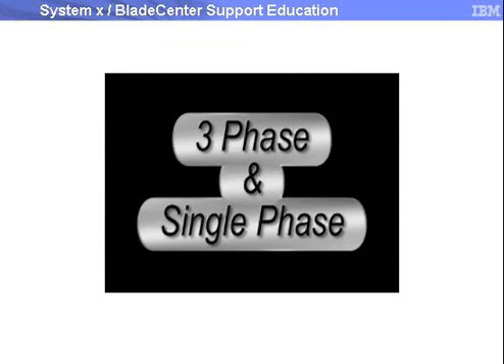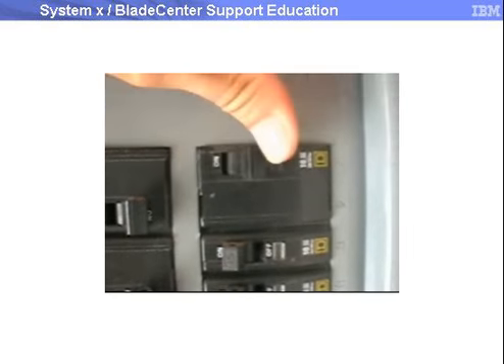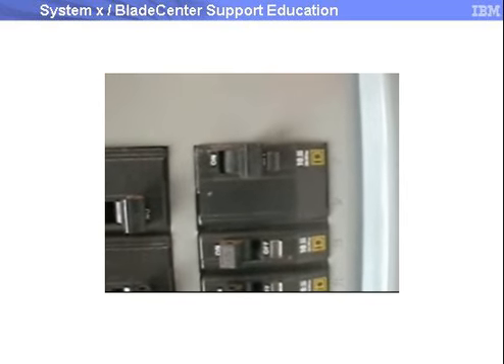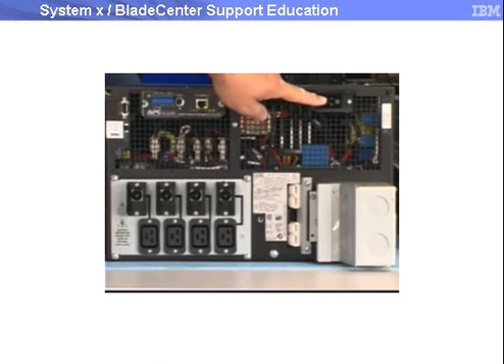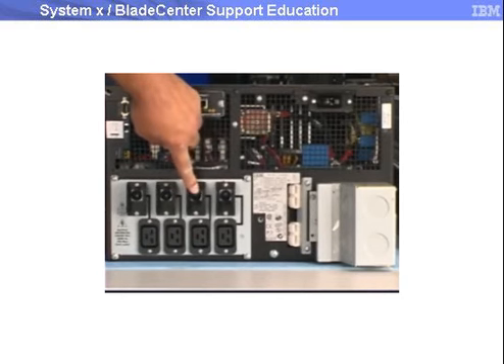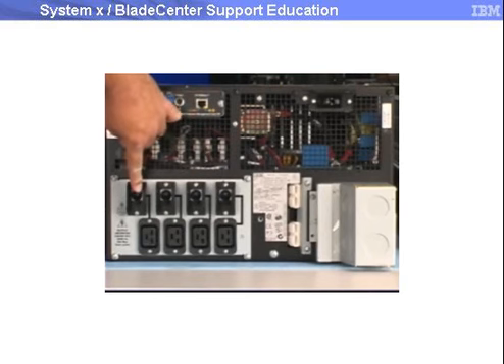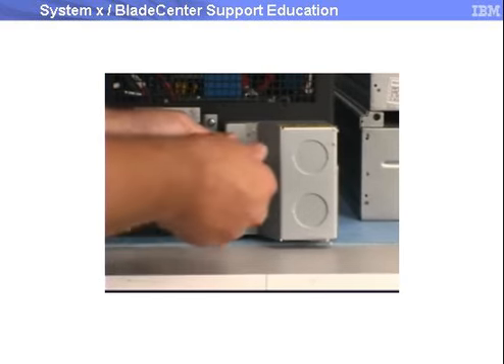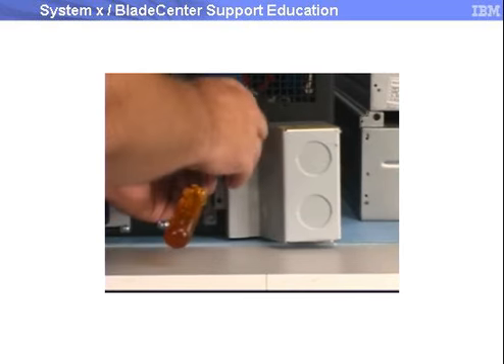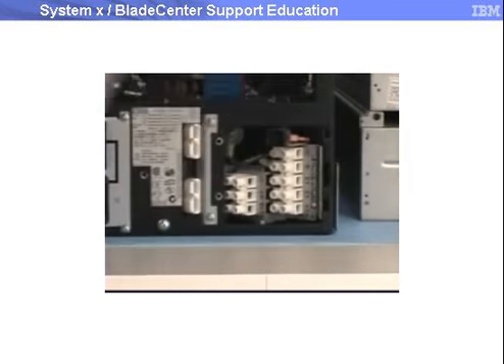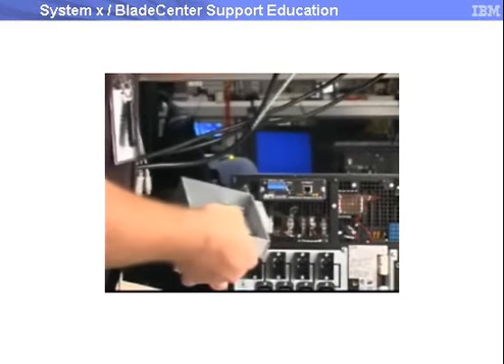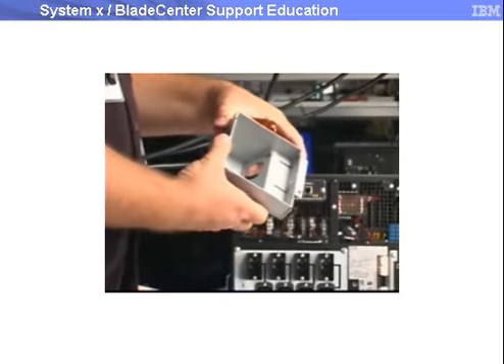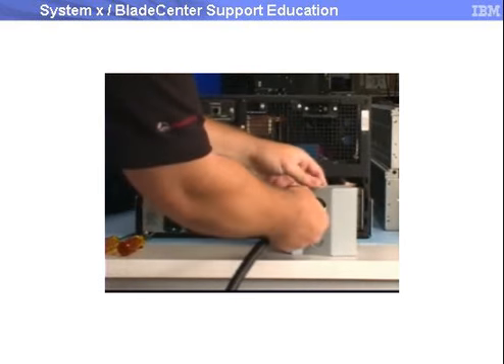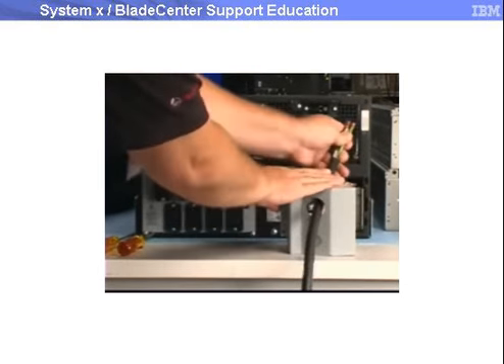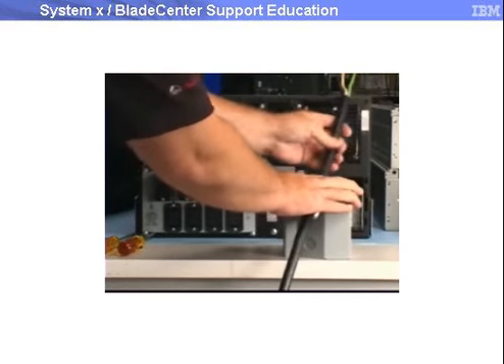To connect to a 3-phase or single-phase electrical input, switch the external distribution circuit breaker to off. Locate the UPS power supply circuit breaker and the utility circuit breakers on the rear panel and switch them to off. Remove the access panel. Remove the circular knockouts on the access panel. Run the input wires through the access panel to the input terminal block. Affix the appropriate strain relief to the wire at the access panel opening.